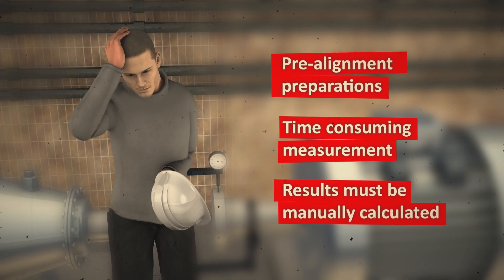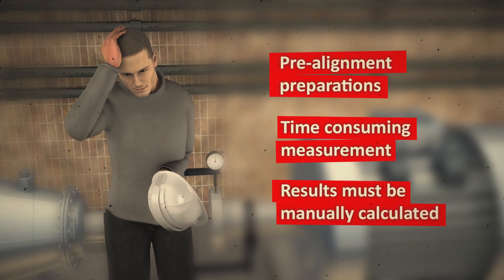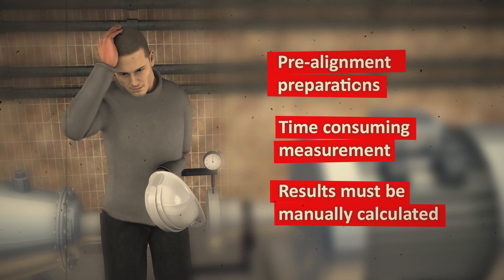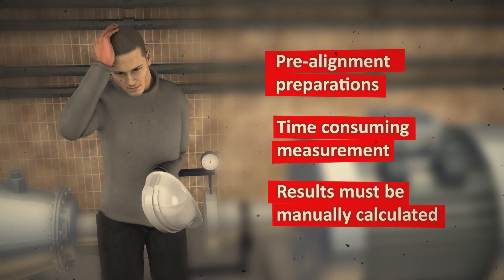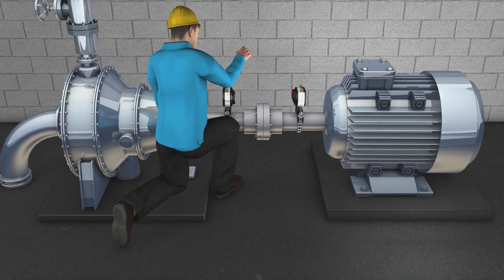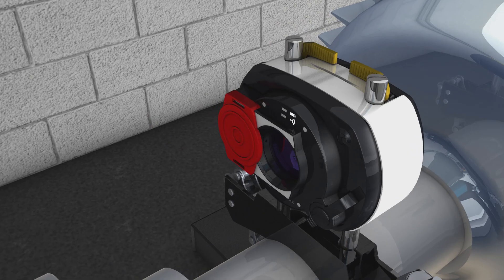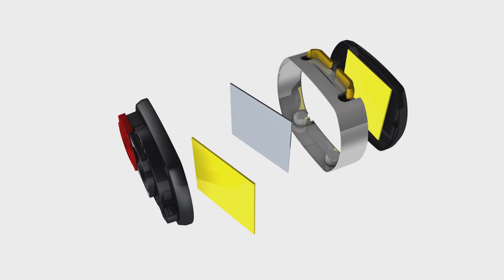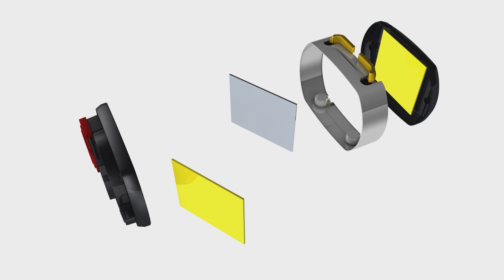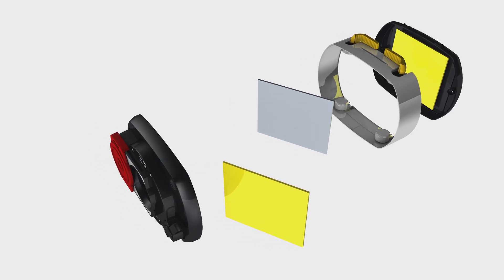Pruftechnik made all this redundant with its unique SensALIGN laser sensor technology. As we just said, measuring angularity and offset always takes at least two measurements. The SensALIGN technology does it all within one single measurement. The single laser beam is shot into the sensor center where it is focused and minimized by an optical lens.